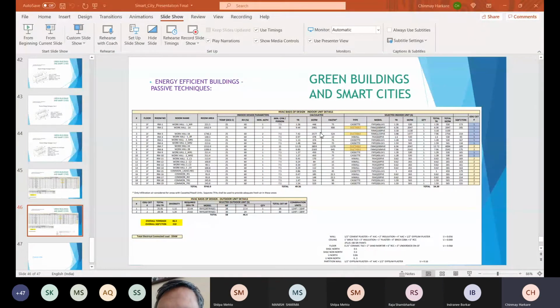We intentionally did those case calculations to demonstrate that for the same room, you need 4 tons under normal scenarios, and by applying those measures, you only need 1 ton. Please keep in mind that such a drastic change will not happen in all general buildings. That is why I also showed you an actual live case scenario where it reduced by about 60 to 65%. It does reduce, but it does not get eliminated completely.